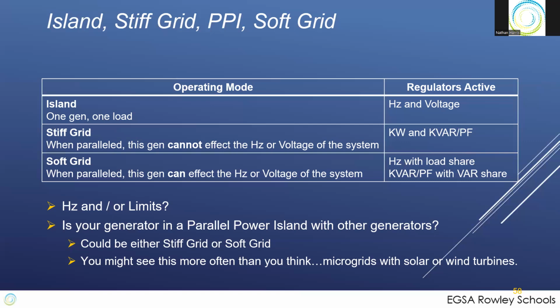We had one in the islands. There was a small island in the Bahamas, where they had a series of smaller units, 300 kW the biggest, around the island, and they connected them together over the years. They never exceeded 12 megawatts on the entire island, the highest they ever had. But they wanted to go to a centralized generation system, so they bought four-meg units so they could have 12 and then a spare available, all out of a centralized power plant. In the US, you bring these four generators online, parallel with each other, close a tiebreaker to utility, go to a kW regulated signal, and just push the power onto the grid to do your startup. The grid can take 16 megawatts at any time.